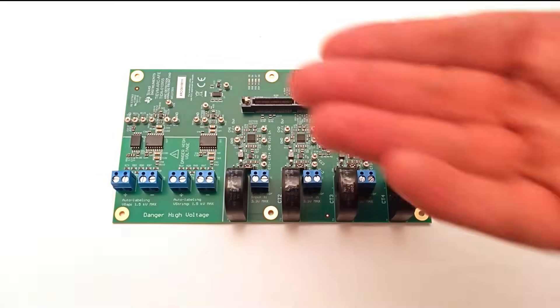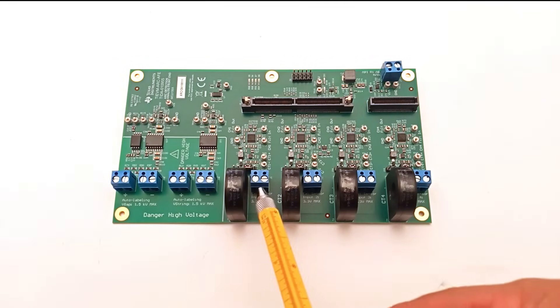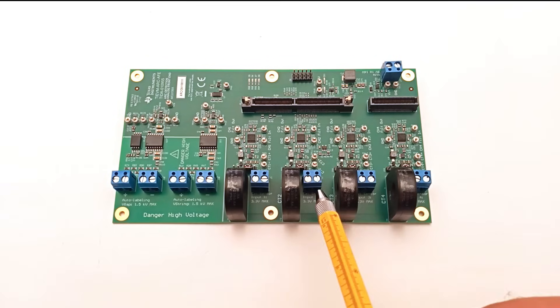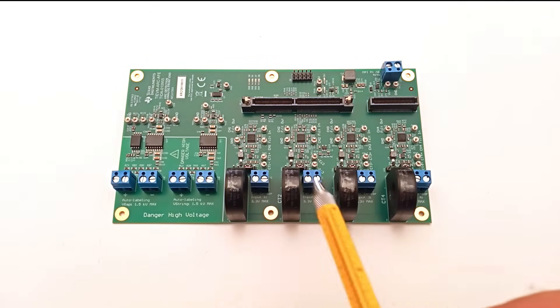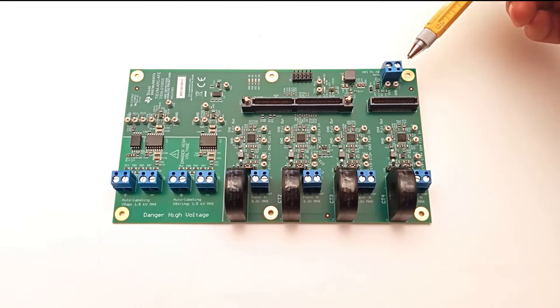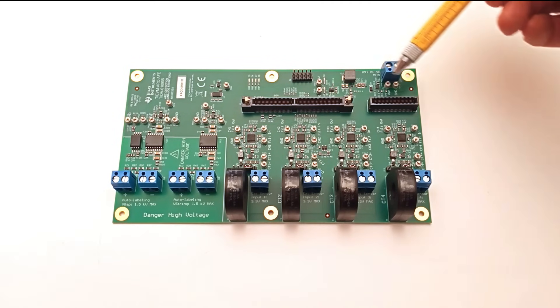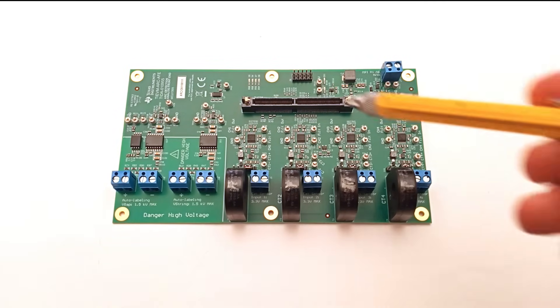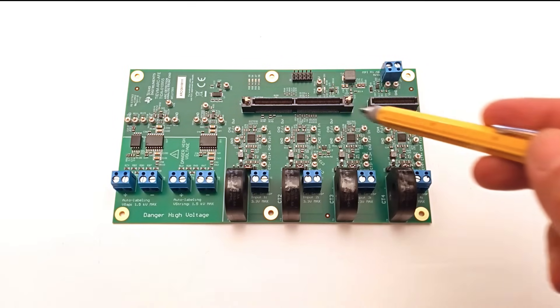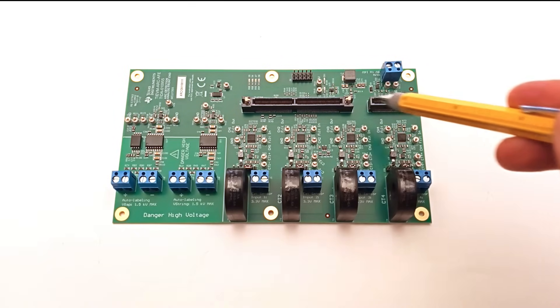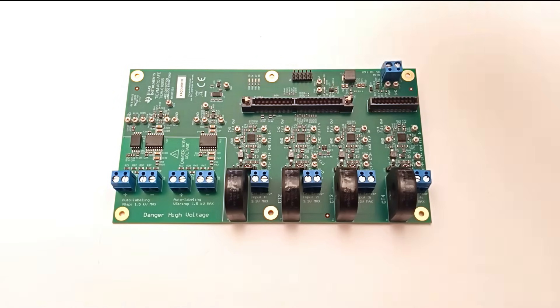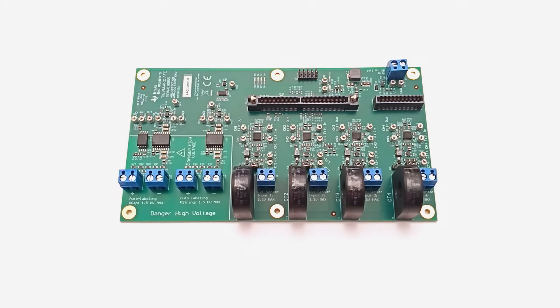Now let's look at the connectors on the board. Refer to the related schematics for more details. J1, J2, J3, J4 are the inputs for external current sensors, one per channel. J7 is the auxiliary power input ranging from 8 volt to 16 volt. J5_1 and J5_2 are the HSEC connectors for the C2000 control card. J6 is the debug header that connects GPIO, voltage lines, and SPI lines.